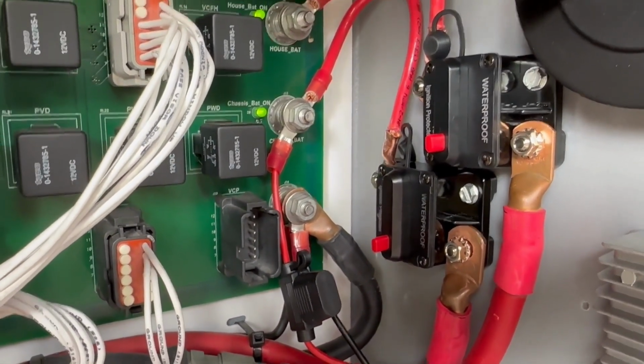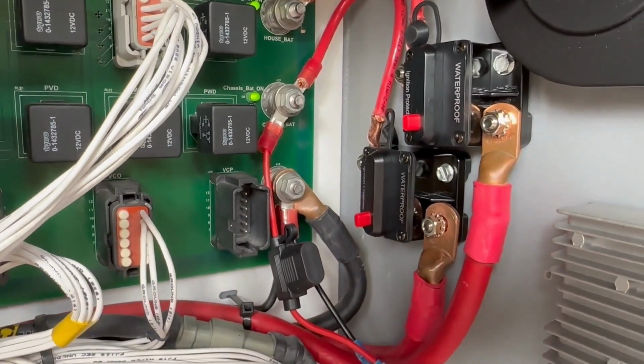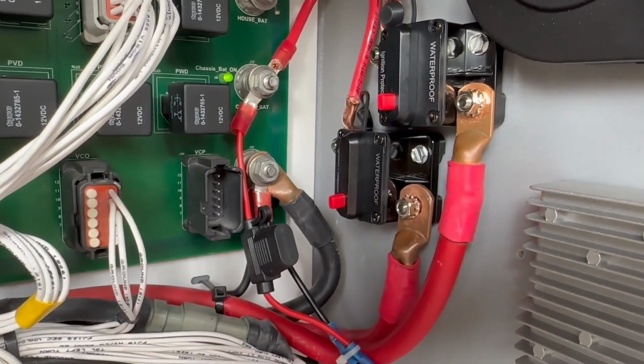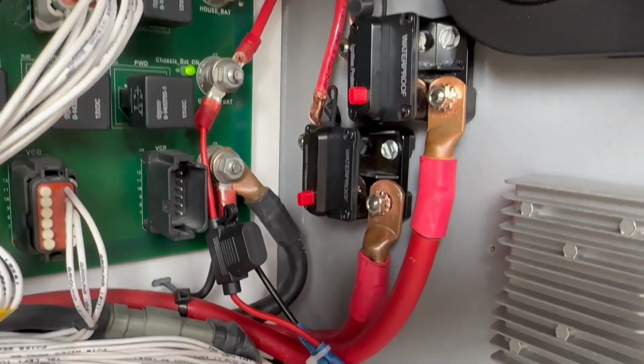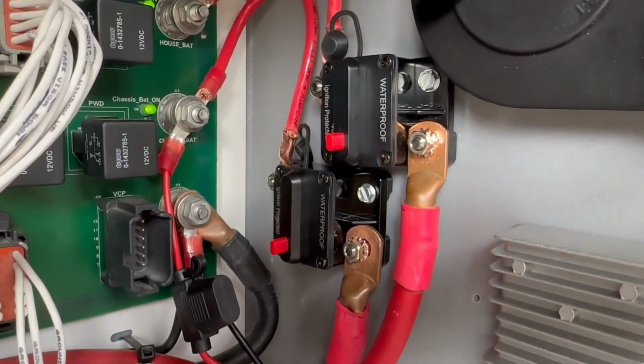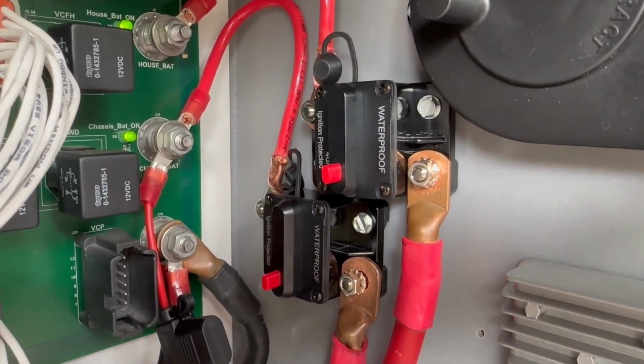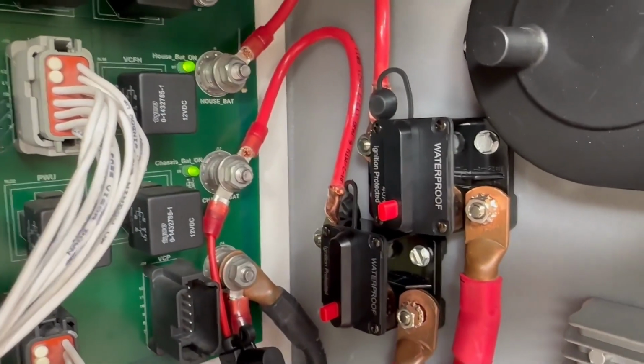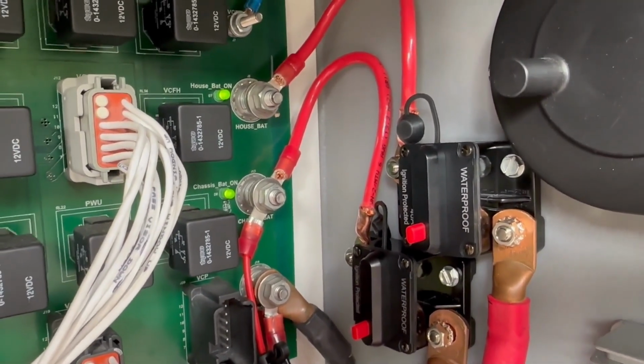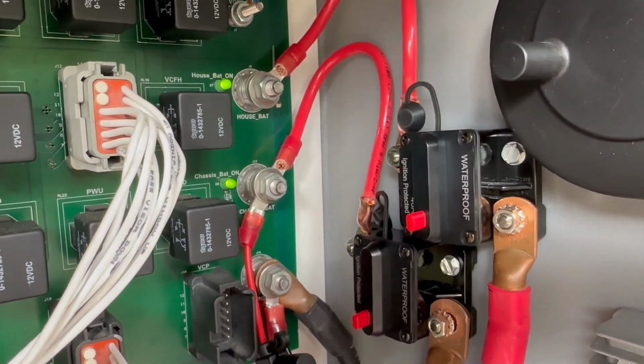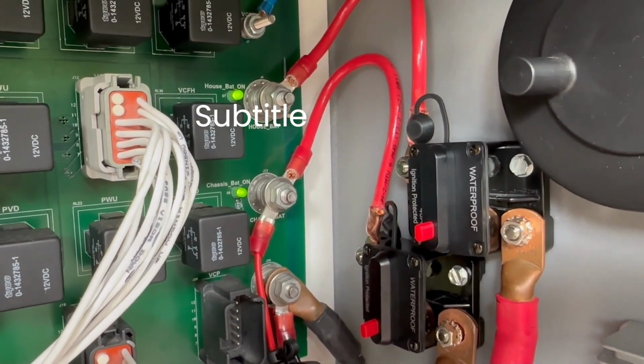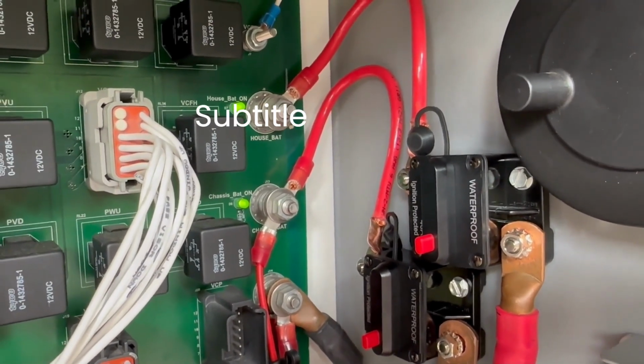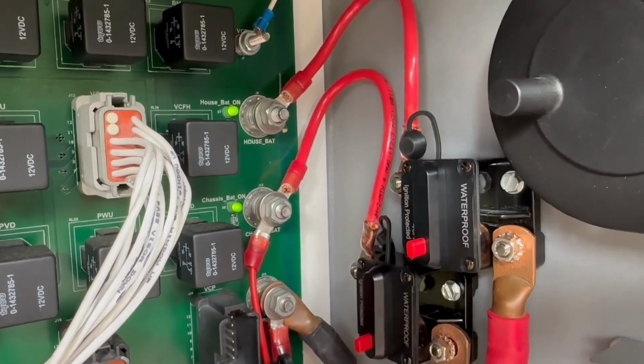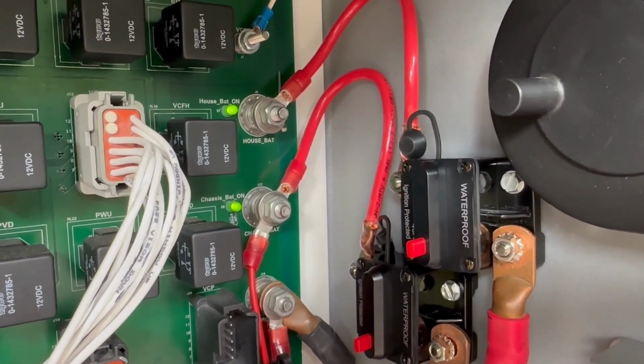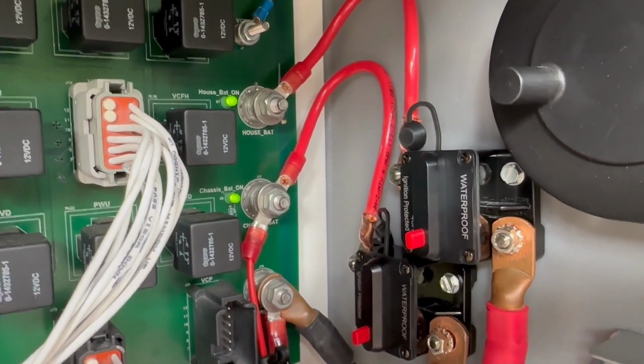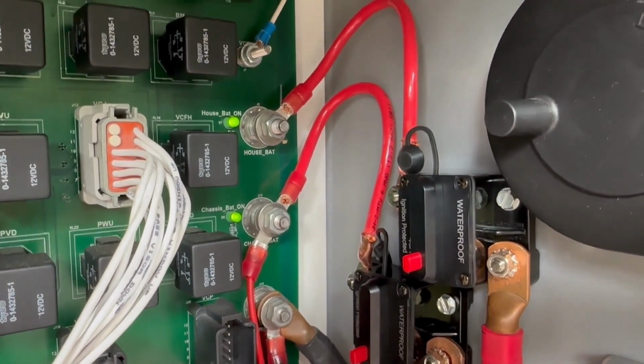So the hardest part of installing these, we're working with the lugs and the existing length of the cables, and that's why you'll see these mounted in such a fashion. We only needed a 6-gauge wire coming out of each one of the breakers over to the original lugs, because that 6-gauge wire is adequate to carry up to 90 amps - pretty sure that's what our calculations showed when we figured that out.